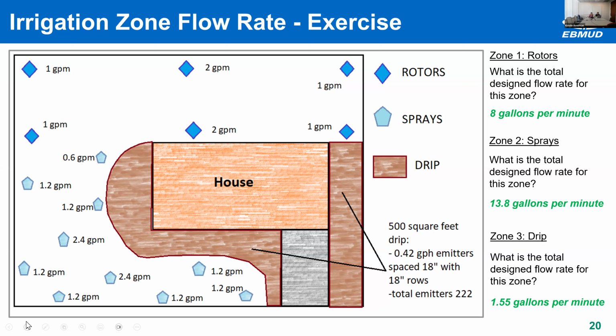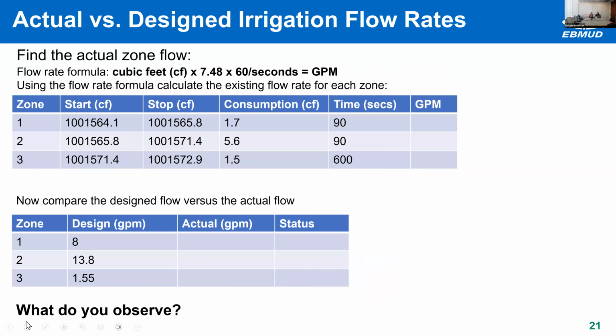Excellent job, everybody. Now let's take this information and compare it to actual flow. We have our design flow, so let's take some meter readings and find out what our actual flow is. On this chart, and as a reminder, the flow rate formula is here as well. We're going to use that to calculate each zone. For zone 1, we have a start and stop reading. We already did this math for you and got our consumption, which was 1.7 cubic feet, and we ran the zone for 90 seconds. What is our flow rate for the zone?